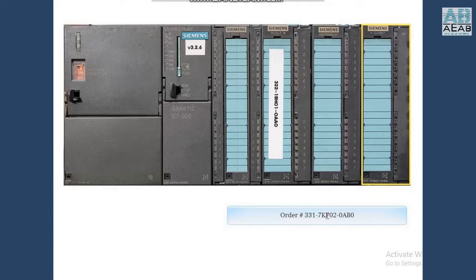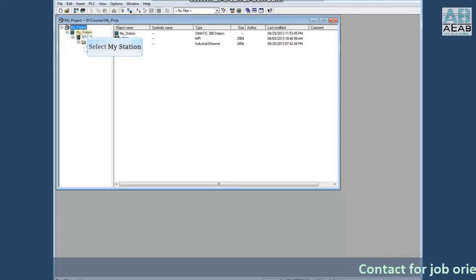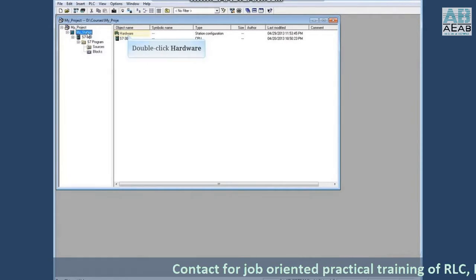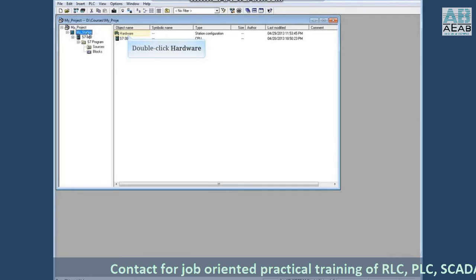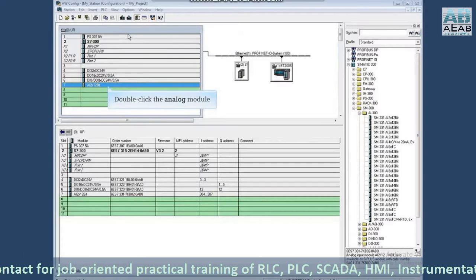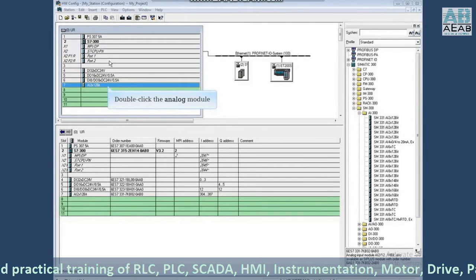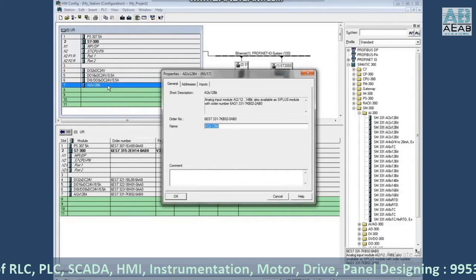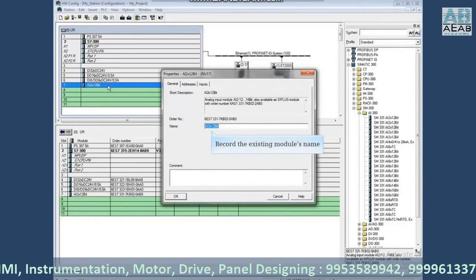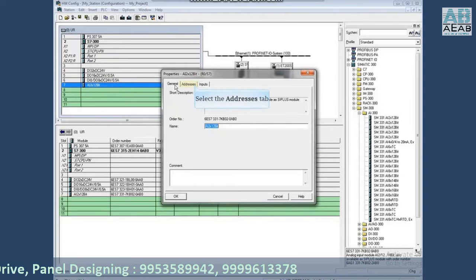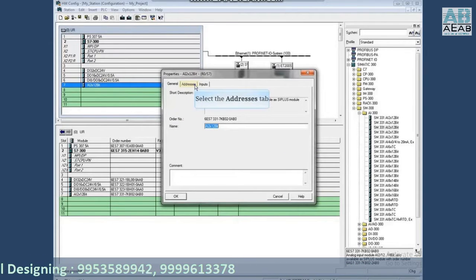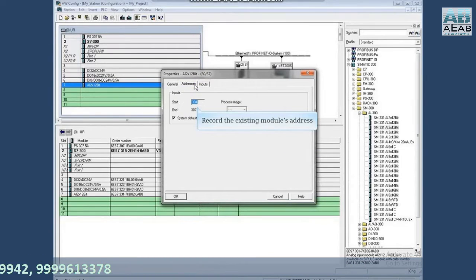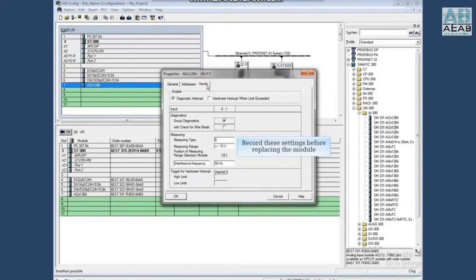To begin, select your station and double-click hardware. Double-click the analog module to open its properties. If the existing module's name is different than the default, be sure to record the name. Select the address tab and record the existing module's address. Select the input tab and record these settings before replacing the module.